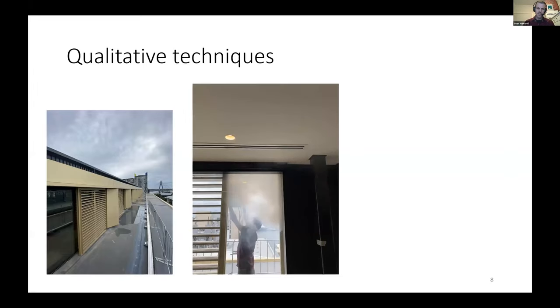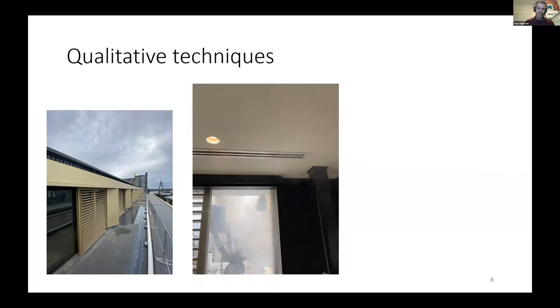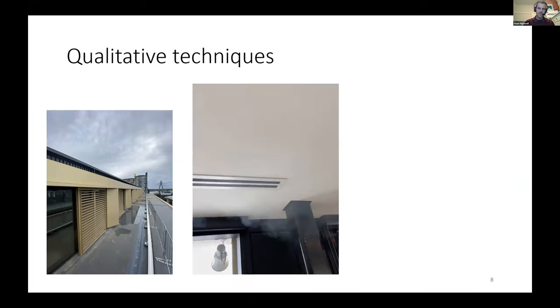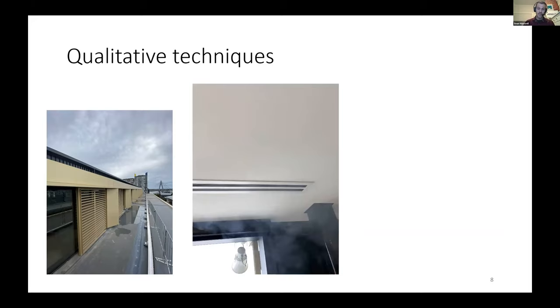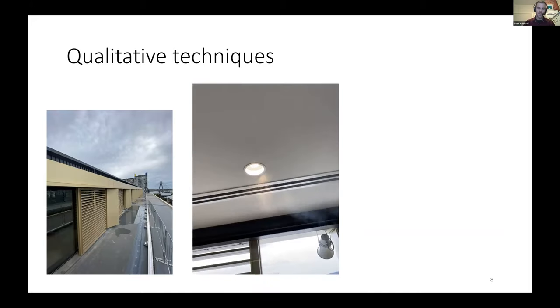So here I am on the outside during a blower door test with a fog machine, and you can see fog coming out of the HVAC and even the light fixtures. I'm spraying fog at this roof junction here, and it's coming out of the lights inside. That's not supposed to happen. So it's pretty interesting when you have the blower door running and you're getting the quantitative number, you can use these diagnostic tools as well to help you find leaks.